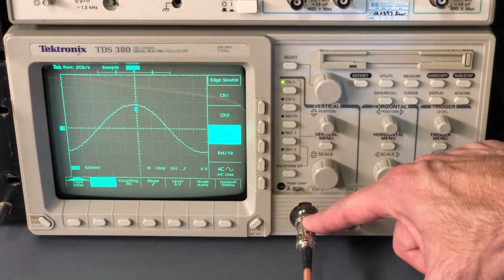Now the adjustment in the service manual says that this waveform should not roll or shift more than 1 division in 10 seconds. So that's ultimately the goal, is to have this less than 1 division of movement after 10 seconds. And if it has even less than that, hopefully it's spot on, doesn't roll at all. But again, it can be up to 1 division in 10 seconds.